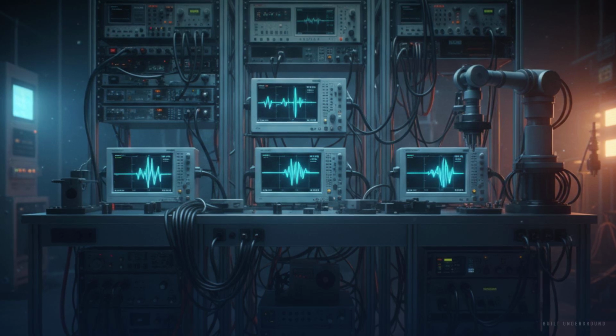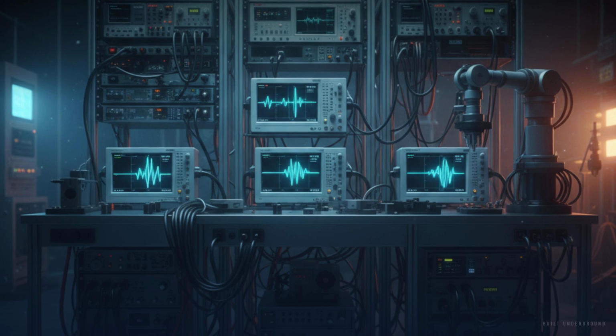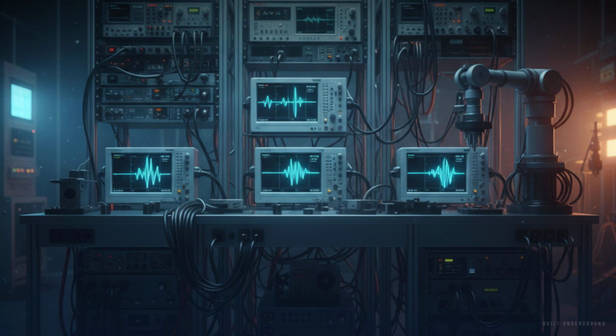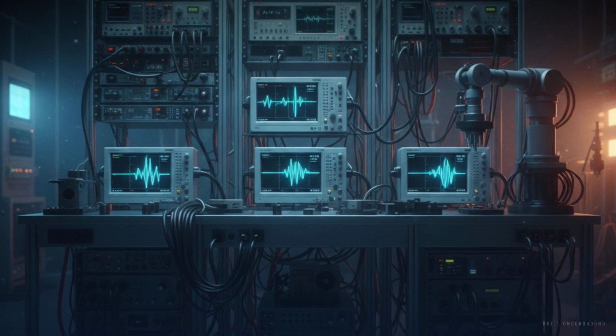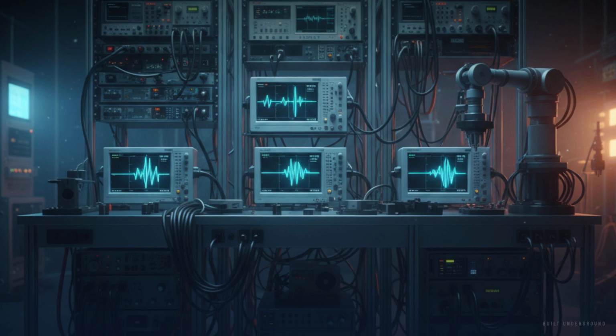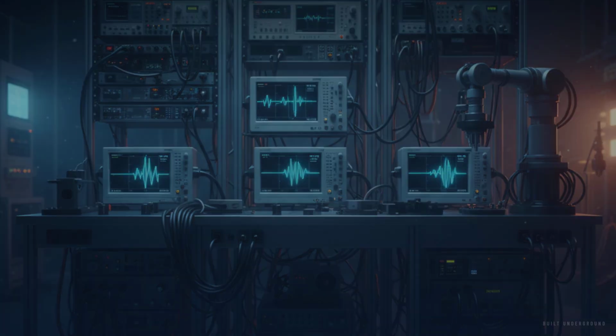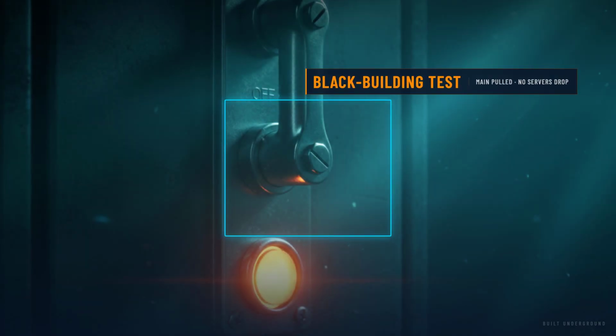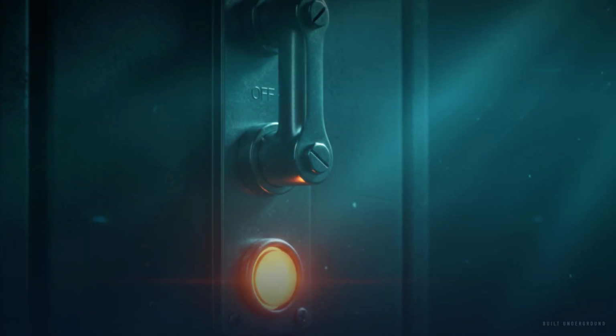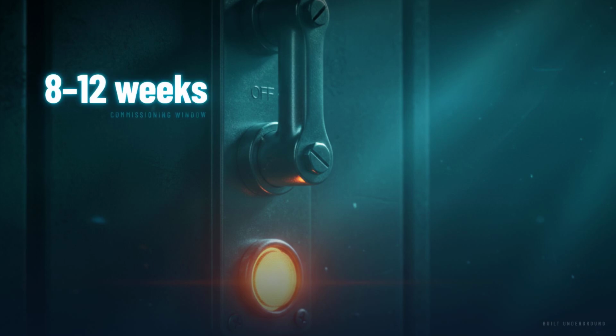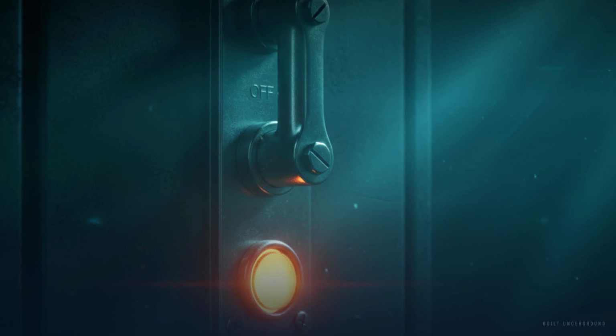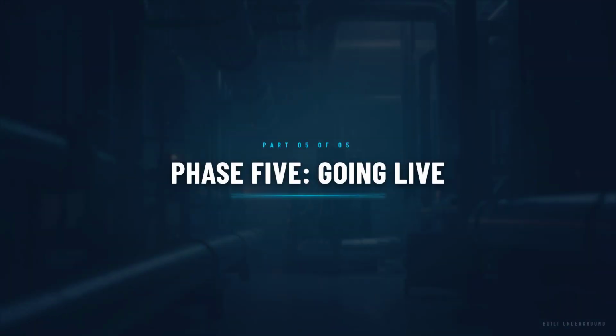The most dramatic test is the full facility failover. Engineers deliberately cut the main power supply and verify that the entire building switches to backup power without dropping a single server. If that test fails, nobody moves in. Commissioning can take 8 to 12 weeks on a complex facility. It is the final quality gate.